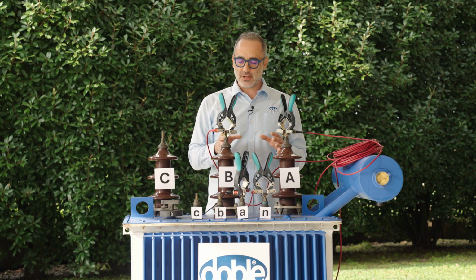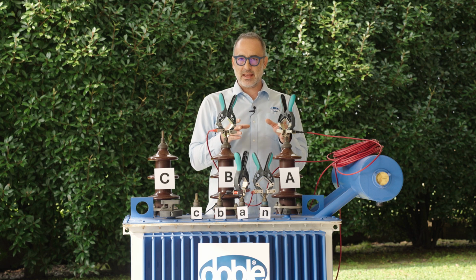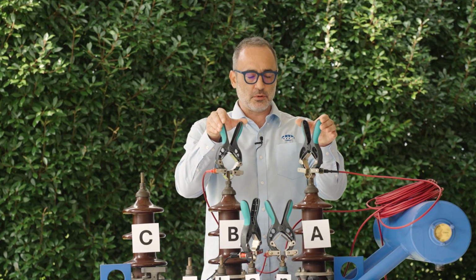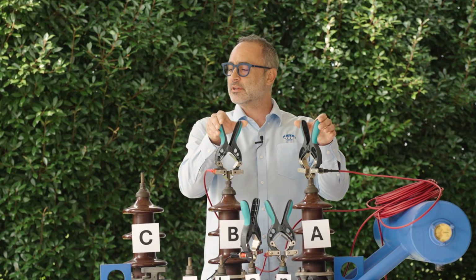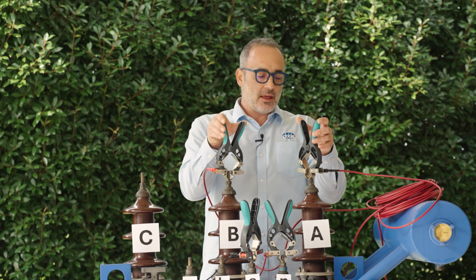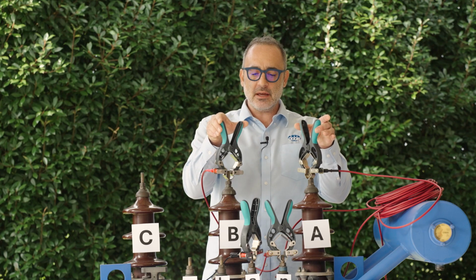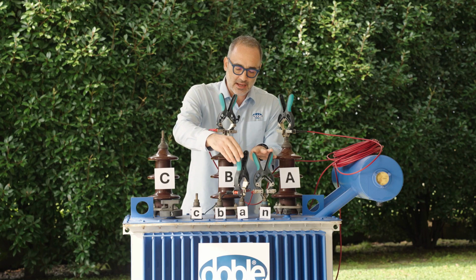Now, for this particular test, for the first test, we will test phase A. Effectively, on the primary side we will connect 2 kilovolt output, but we will not generate 2 kilovolt, we will generate 200 volts.